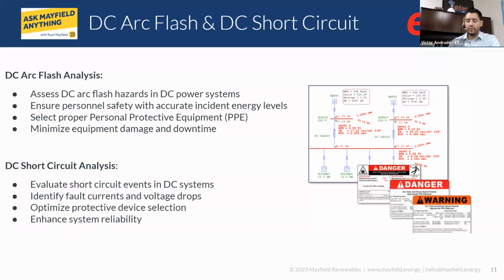Mm-hmm. Yeah. So some renewable sites are extremely unique in the sense that we have seen large PV sites that, number one, have aluminum cable. So that alone makes them unique, because in the commercial and industrial world that we see, it's always copper. And yes, we have a very large aluminum cable library in the software to model those instances, but also the other uncommon installation is gear, right? Outdoors gear, enclosed 34 or 34.5 or 35 kV gear. The Arc Flash AC standard, which is the IEEE 1584, currently only goes up to 15 kV, but ETAP has developed a method for calculating incident energy or producing these Arc Flash labels that you see on the screen on locations that are above 15 kV.